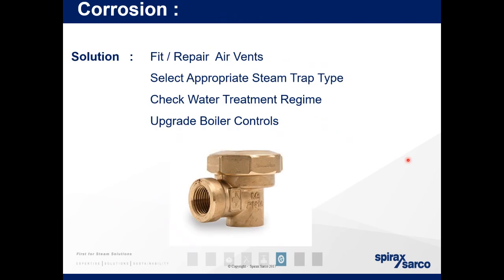So solutions: we can fit and repair air vents. Air vents, I would say, are very essential to your system, especially when we use vacuum breakers too. It's slightly off topic, but many of you will find that you have leaking gaskets on systems. When your system's firing up and running, you'll see leakages between the gaskets, between flanges. A lot of the time, that can be cured by adding air vents, not excessively, just one or two.